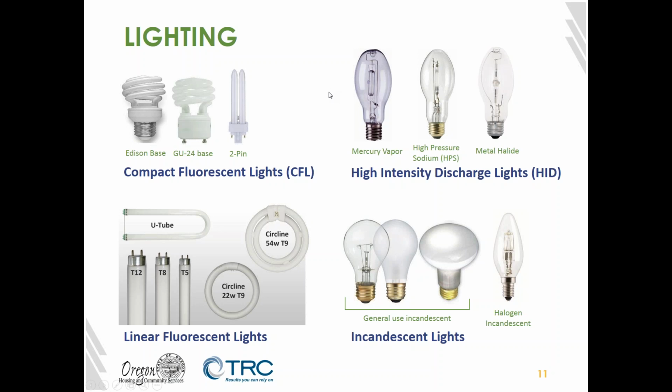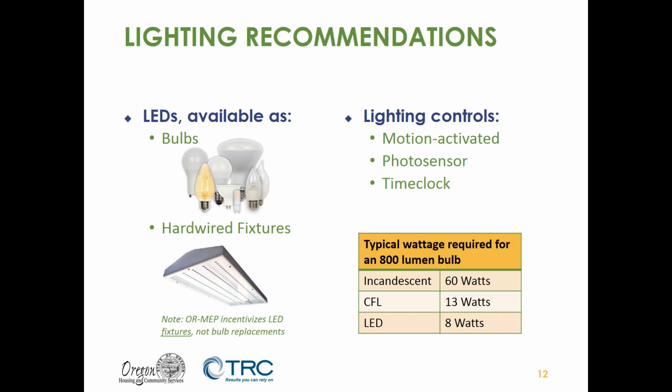For the last couple decades, the standard efficient lighting option for those would have been fluorescent lights. So you'll see a lot of those, compact fluorescent or linear fluorescent. But now we have LEDs, which have gotten to a point where they are just as stable as any other light source. And they tend to last longer, and they're about 30 to 40% more efficient than fluorescent, and they use about 10 to 20% of the energy of incandescent. So they're much more efficient than those.